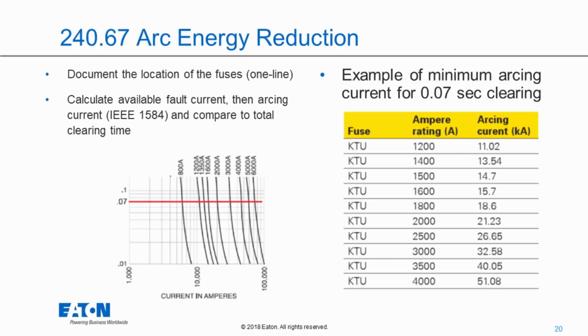Once I have that value, then I have to calculate the arcing current, and the only known method that I'm aware of today is to use IEEE 1584, or at least that's the very best method to use. Once we find and calculate the arcing current, we then have to compare that to the total clearing time of the fuse. So as you can see here, we need to consult the time current curve, and I have an example shown there. We find the arcing current on the bottom axis, go up until I hit the fuse clearing time, then proceed over to the left to determine the clearing time, and I'd need to be at 0.07 seconds or less.